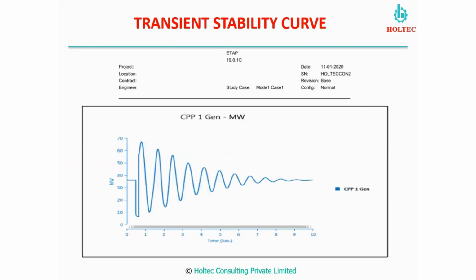Then we examined all these curves. This is the generator megawatt curve. If we find that we are able to retain stability, and it is validated for all the sources, we can recommend that our setting should be like that: in such a transient, the relay operation time should be less than 150 milliseconds. In that way we can ensure the system will be totally safe for such transients, which happen due to fault conditions, abnormal load flow, switching of generators, or any major load switching off or load throw.